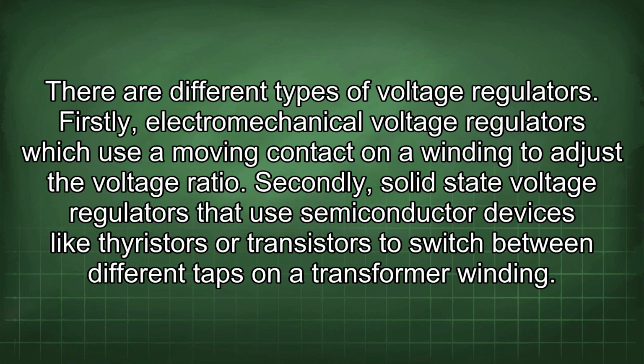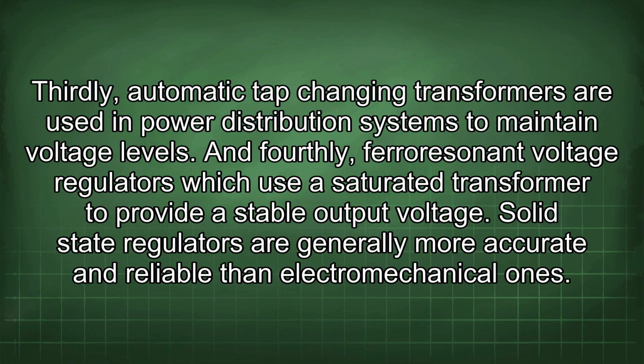There are different types of voltage regulators. Firstly, electromechanical voltage regulators, which use a moving contact on a winding to adjust the voltage ratio. Secondly, solid-state voltage regulators that use semiconductor devices like thyristors or transistors to switch between different taps on a transformer winding. Thirdly, automatic tap-changing transformers, used in power distribution systems to maintain voltage levels. Fourthly, ferroresonant voltage regulators, which use a saturated transformer to provide a stable output voltage.